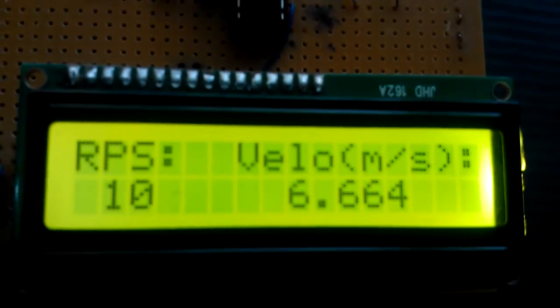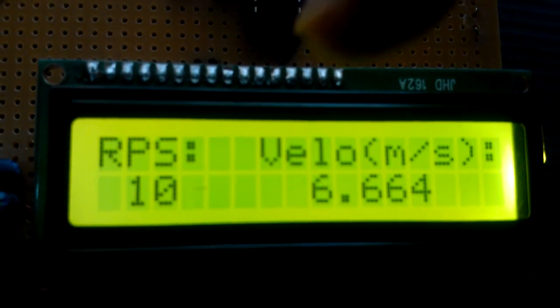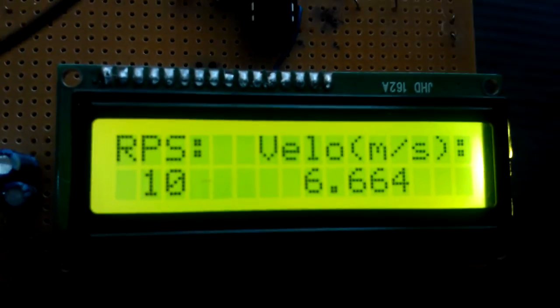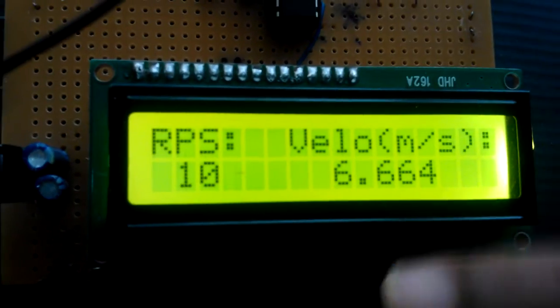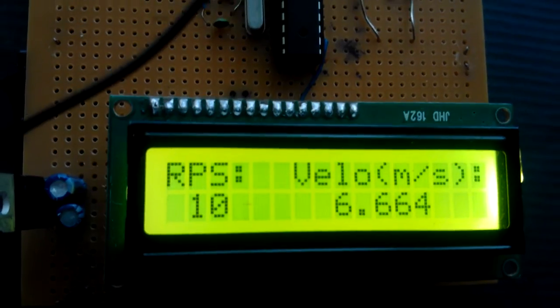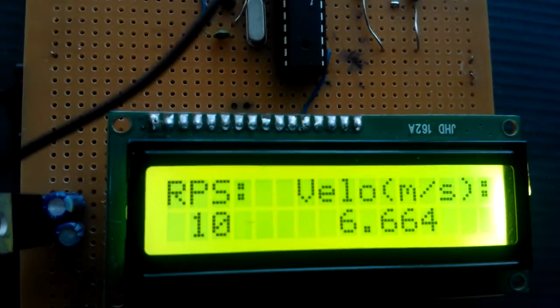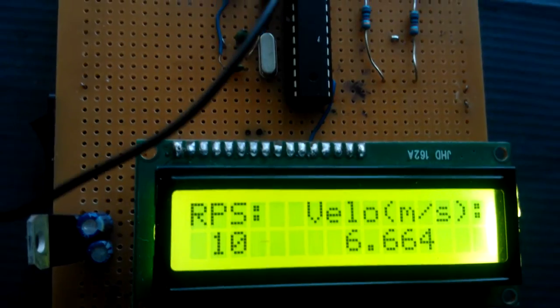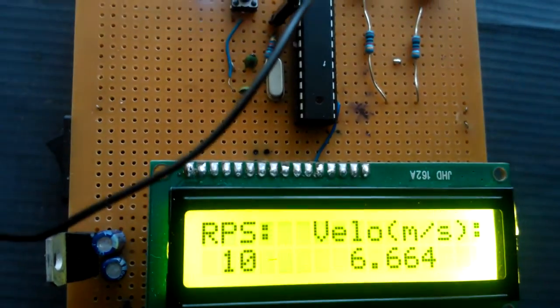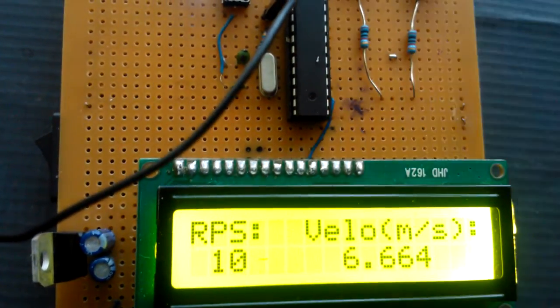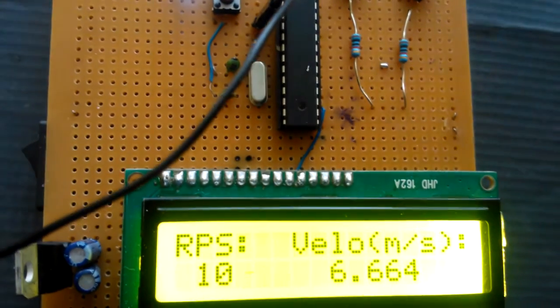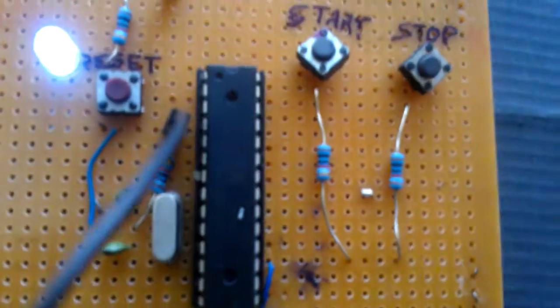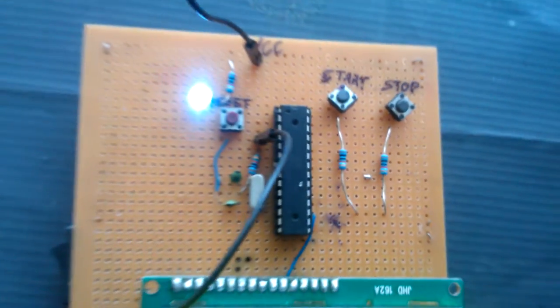Revolutions per second - the last count is 10 - and the velocity of water flow is 6.664, calculated using the formula V = R*M + C, where R is the revolutions per second, M is the slope of the graph drawn between velocity and RPS, and C is the minimum velocity of water for which the Pelton wheel starts rotating.